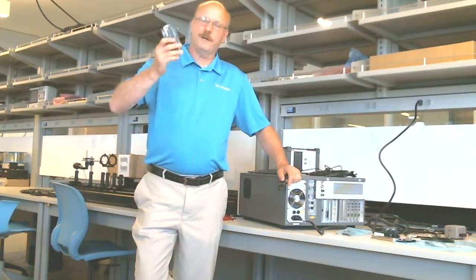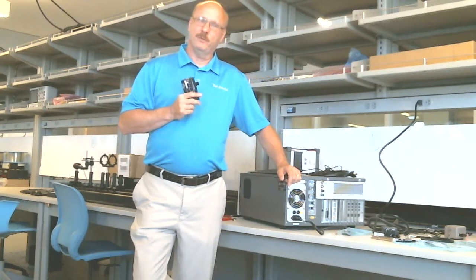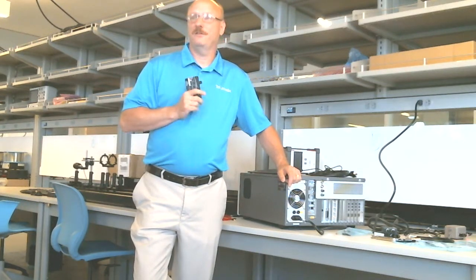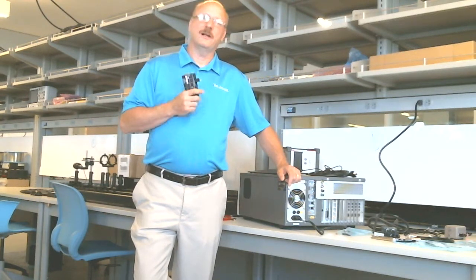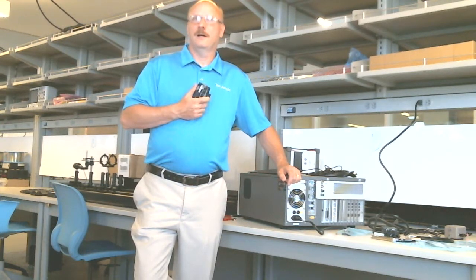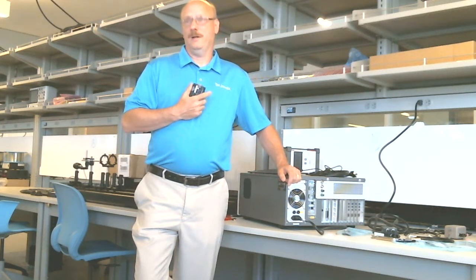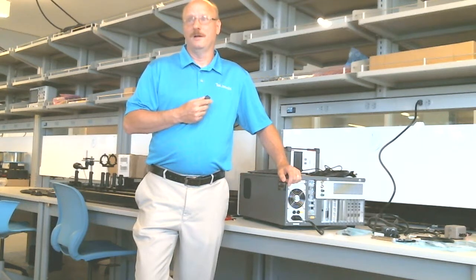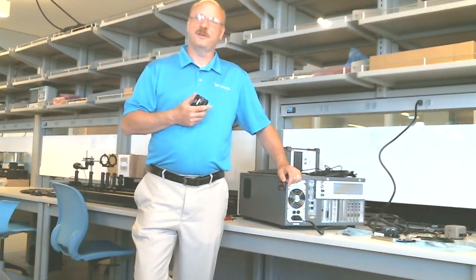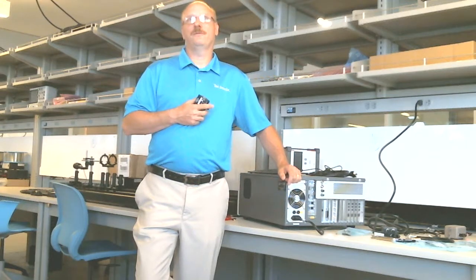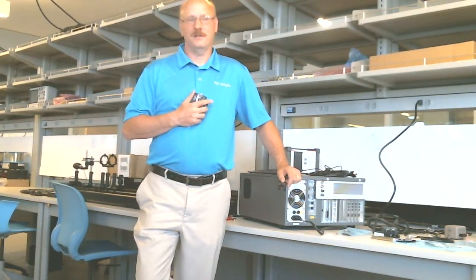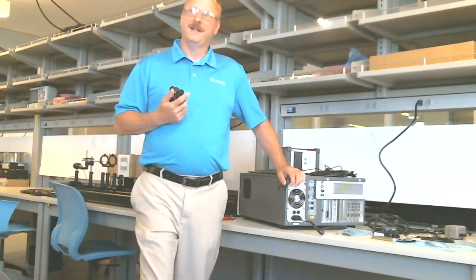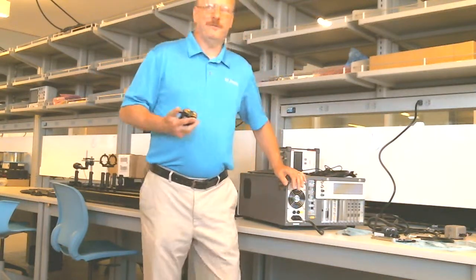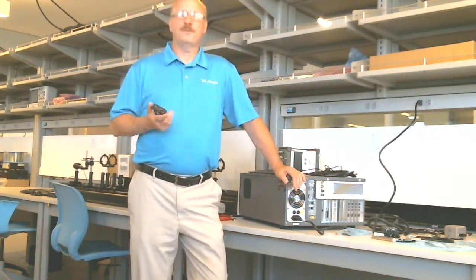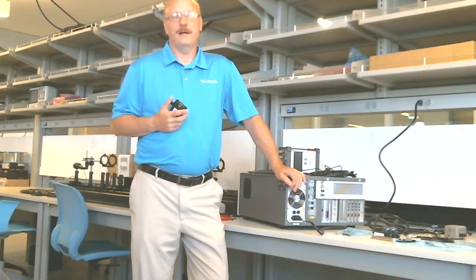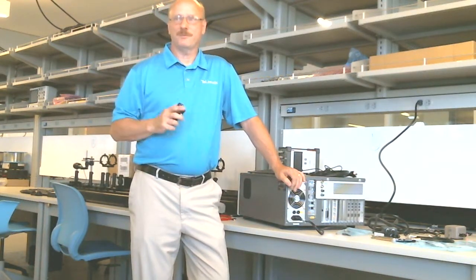But since you've only got 1 preamp, that means only 1 channel will be capable of very high sensitivity current measurements, so that it can measure down to its lowest range of 10 attoamps, 10 to the minus 18. Without the preamps, you can measure 10 femtoamps, which is still pretty darn low, right? So you just got to know, if you need to go below 10 femtoamps, you need to be connected to channel 1 on that pin, because that's where your preamp's going to be.